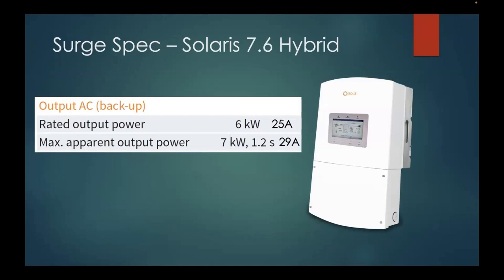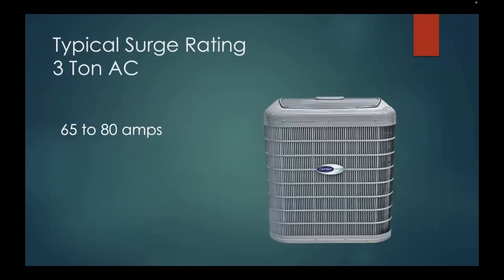Now there are other ways around that—you can cheat a little bit using what's called a soft start kit. Soft start kits have been used in the off-grid world forever; it's just a box full of capacitors that reduces the surge current on the battery inverter. You'll need one for each large device, and they run anywhere from $300 to $500 depending on the size you need.